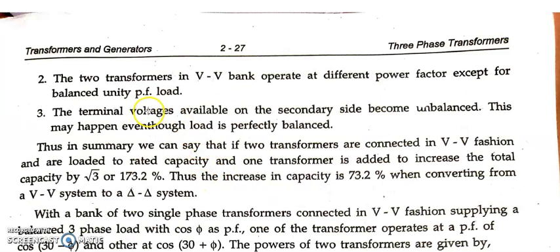Second one, the two transformers in a VV bank operate at different power factors, except for a balanced unity power factor load. Meaning even if you connect a balanced load, the two transformers which are connected in VV connection both operate at different power factors. It is not like the load is balanced and the power factor of both of the transformers is the same. It is not like that. Power factors of both the transformers are different.